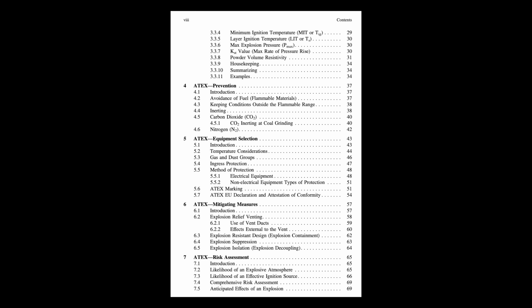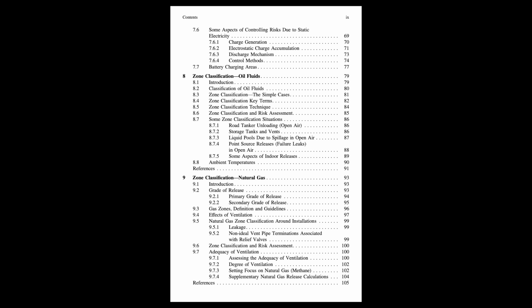Pretty much. Then, similar to gases, dust clouds have a lower explosive limit, LEL. It's the minimum concentration of dust suspended in air needed for an explosion. What sort of concentrations are we talking about? Typically, it's in the range of 20 to 60 grams of dust per cubic meter of air, although some can be higher. The guide gives a really striking visual for this. Oh, yeah. It says a coal dust cloud at just 40 g/m³ would be so dense you wouldn't be able to see a standard 25-watt light bulb from only 2 meters away.